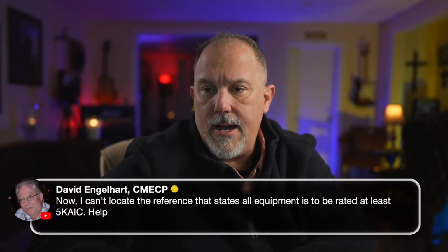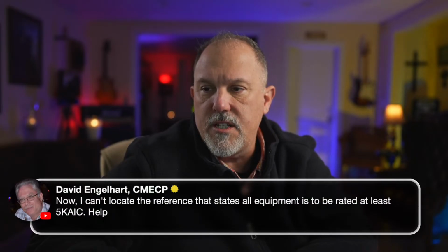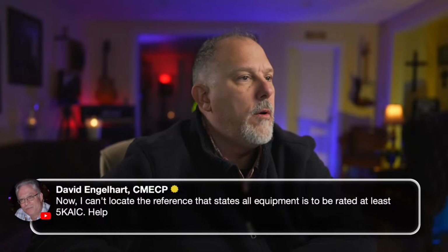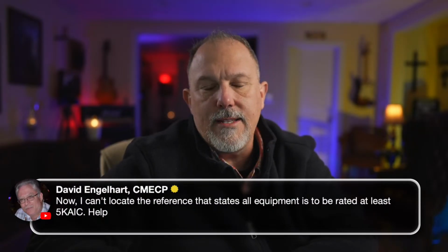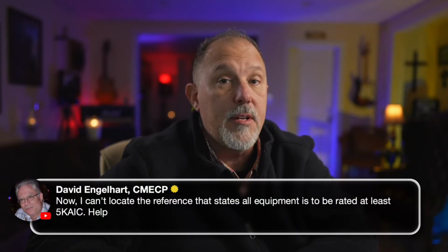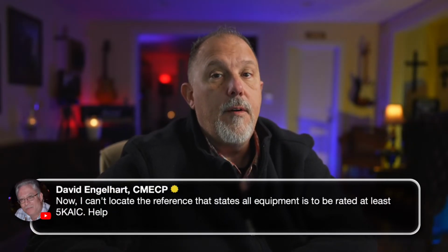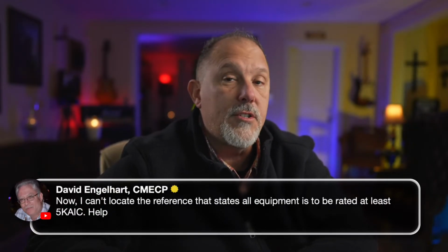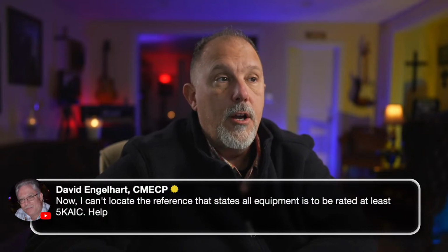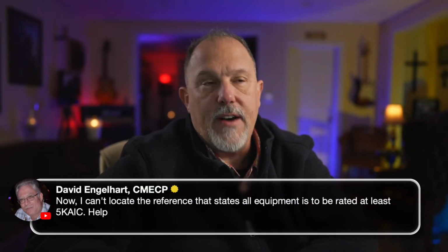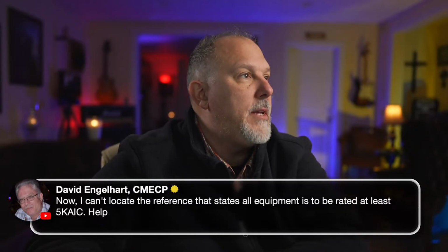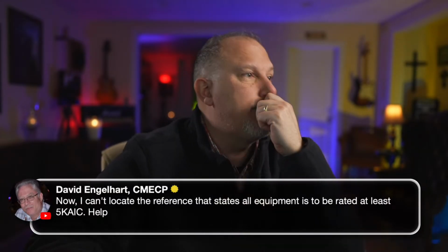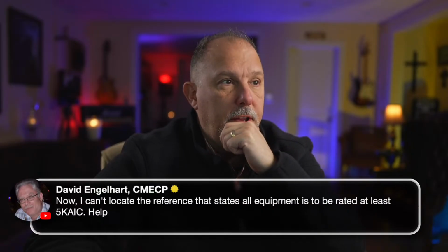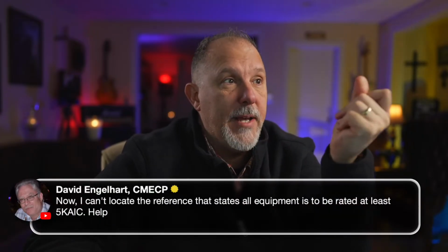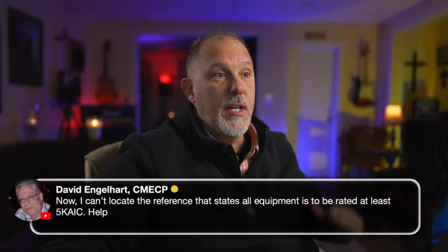David Engelhardt says, now, I can't locate the reference that states all equipment is to be rated at least. No, you know what, David? Here's my opinion. I believe you're thinking of circuit breakers. All circuit breakers that are not labeled have a 5 kA interrupting rating, and that would be in Article 240. Article 240 is for you and me.